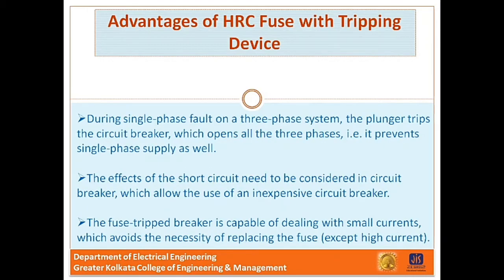Next, advantages of HRC fuse with tripping device. HRC fuse with a tripping device has several advantages over a HRC fuse without tripping device. At first, in case of a single phase fault on a three-phase system, the plunger operates the tripping mechanism of circuit breaker to open all the three phases and thus prevents single phasing.